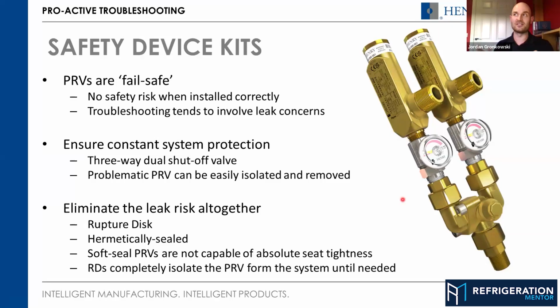The advantages of this are that PRVs, and it's kind of a common misconception, and it's becoming more prevalent as, rightfully so, the industry is becoming more sensitive to leaks and trying to reduce leak rates everywhere. But there's a common misconception out there that a PRV is capable of absolute seat tightness and it should never leak. Now, from a technical point of view, everything leaks. Welded joints leak, so there's always leak there. But when you think about a PRV, and we're talking about welded joints, I think that 3 grams a year is kind of the term in EN 378 that's banded around as being acceptable as leak tight if something's 3 grams a year of refrigerant leakage. And that's talking about welded joints.